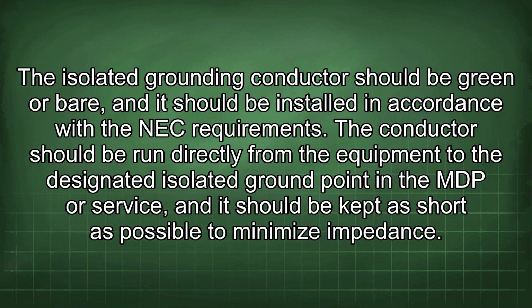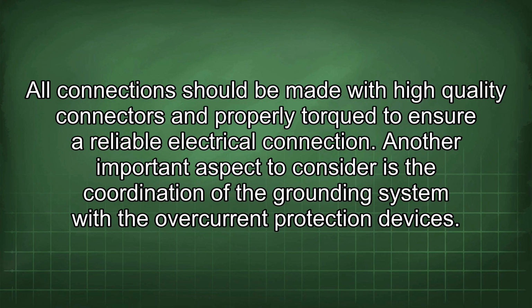The isolated grounding conductor should be green or bare, and it should be installed in accordance with the NEC requirements. The conductor should be run directly from the equipment to the designated isolated ground point in the MDP or service, and it should be kept as short as possible to minimize impedance. All connections should be made with high-quality connectors and properly torqued to ensure a reliable electrical connection.